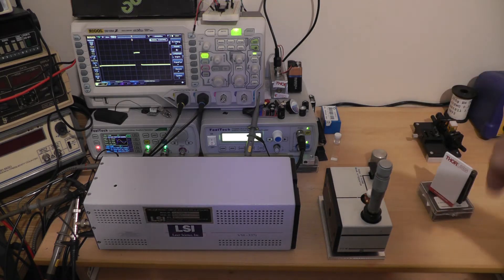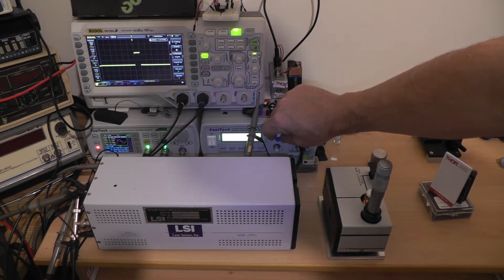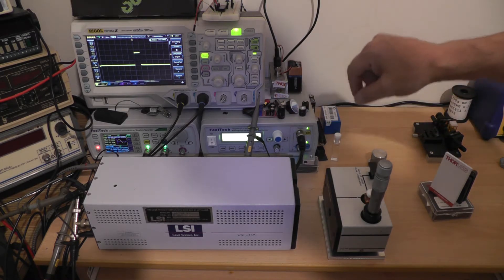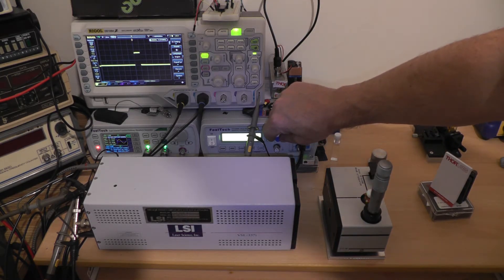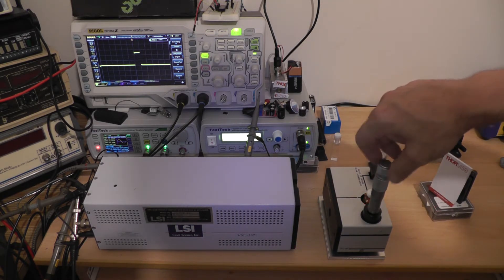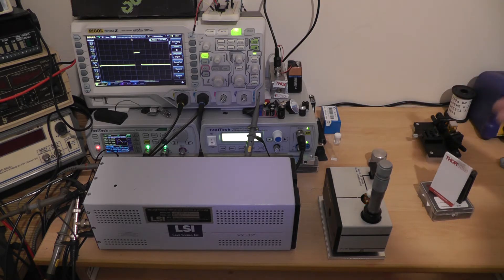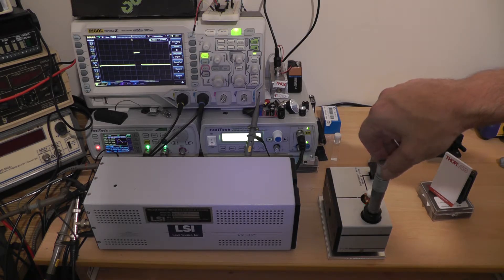Pretty cool. And obviously because it's got a new plasma cartridge now we can rack this right up to about 20 Hertz and it will quite happily - perhaps not with Rhodamine, we'll turn it down just a hair - we'll maybe get 17 Hertz. We can still get reasonable output. This spot almost looks continuous at this point - it's not so far off. I mean you can see the flicker but it's reasonable.